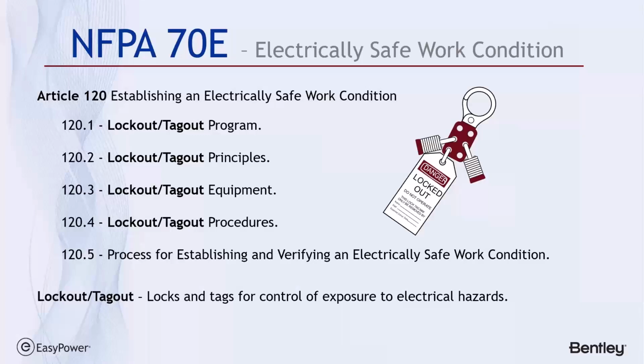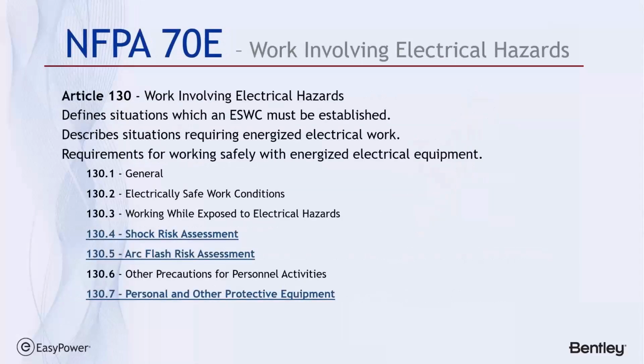The third part of the requirement is to have a mechanical notification process that prevents re-energization by anybody that's involved with electrical work on the equipment. That's represented by the lock and tag out. If there are any locks on there, then I can't re-energize the equipment until they're cleared. All this is described in NFPA 70E, and the forms are stuff you can copy from the annex.